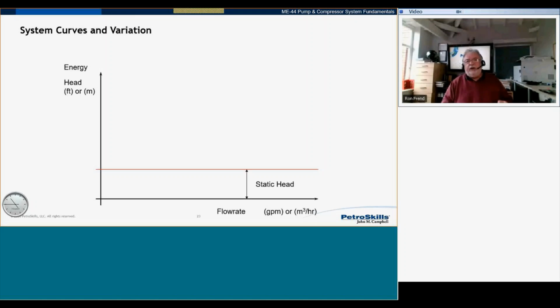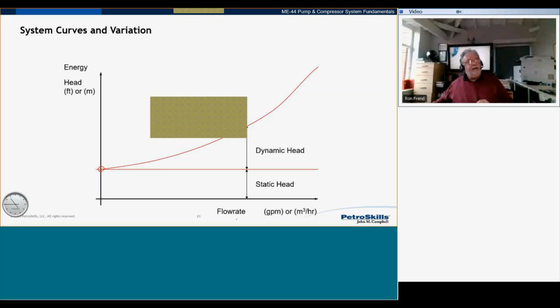Next, I'm going to add my friction loss. Now, we calculated the friction loss at a particular flow rate. But we said at 0 flow, there's obviously 0 friction loss. So I now have 2 points on my curve. I've got 1 point there where the friction loss is 0, and somewhere up here is where my friction loss was at the particular flow. And remember, we know the relationship between the two of these. For my particular system, we calculated the head is proportional to the flow to the power of 1.82. Or what I could do is calculate this for different flows. So that's not too difficult to do. So what we end up with is a system curve.